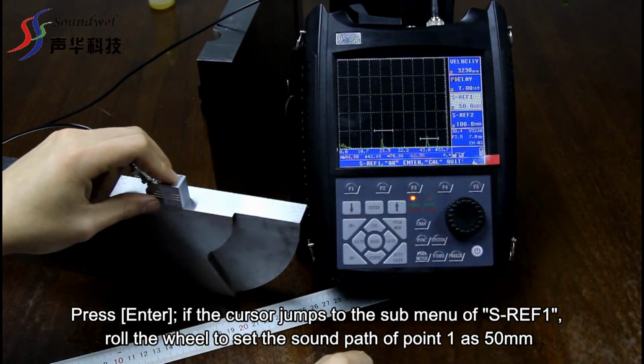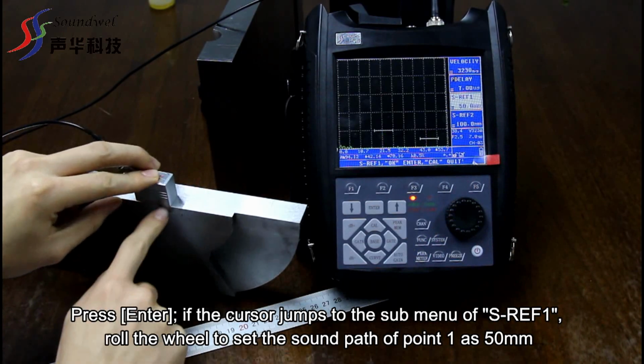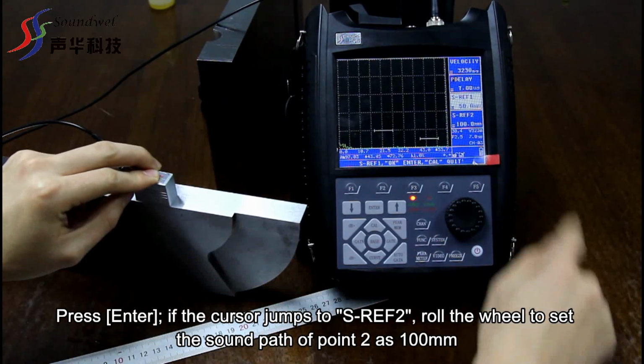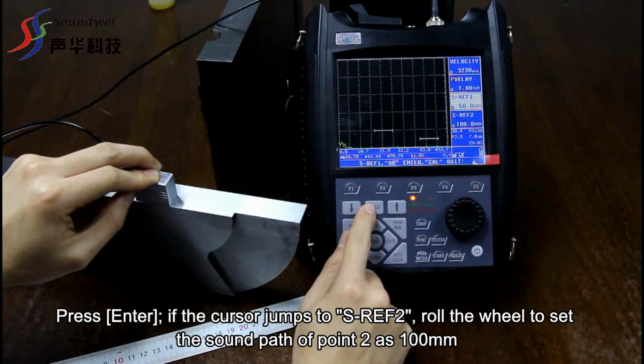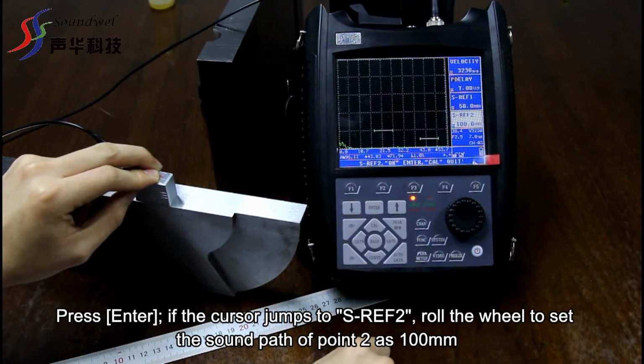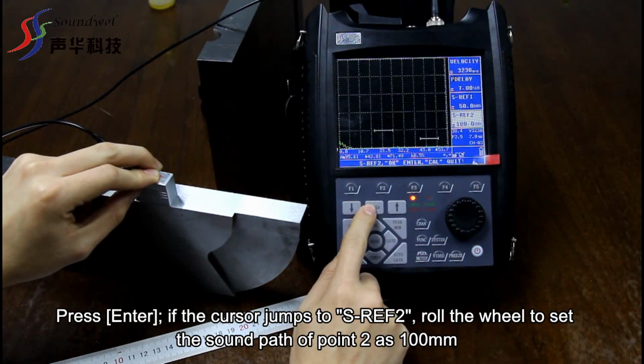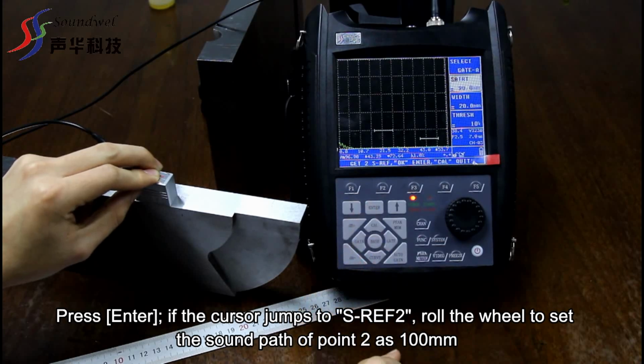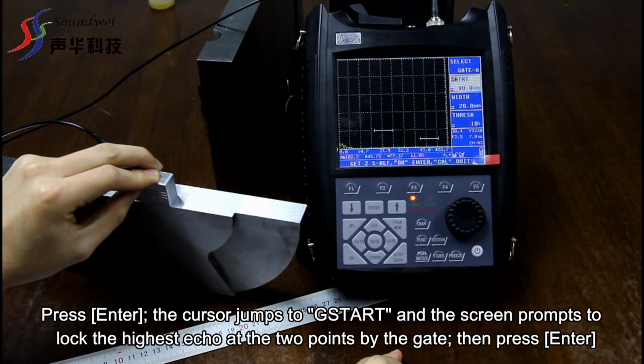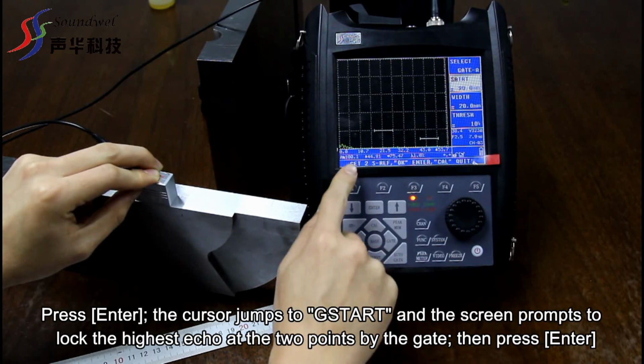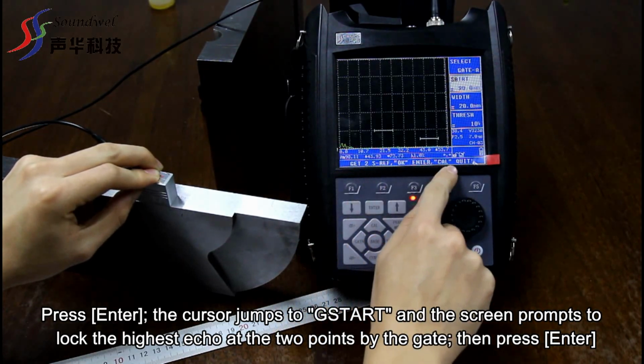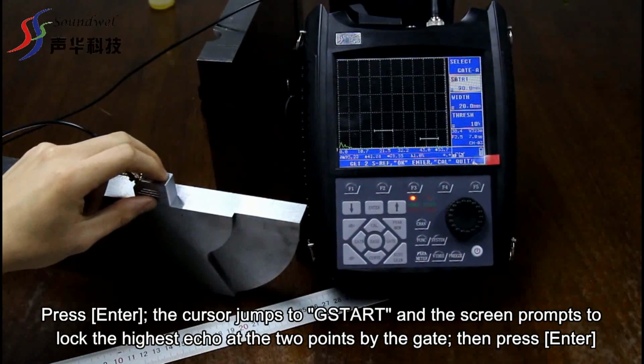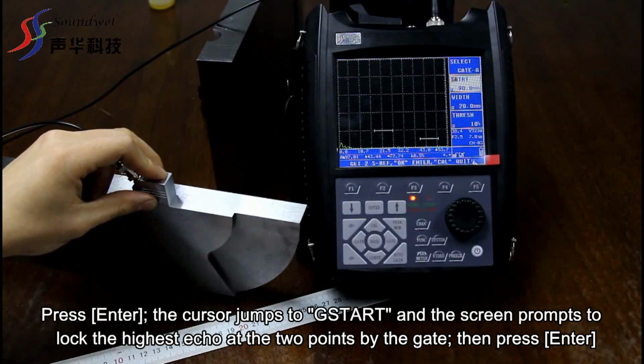Roll the wheel to set the sound path of point 1 as 50 millimeters. Press Enter if the cursor jumps to SREF2. Roll the wheel to set the sound path of point 2 as 100 millimeters. Press Enter. The cursor jumps to G-start, and the screen prompts to lock the highest echo at 2 points by the gate. Then press Enter.